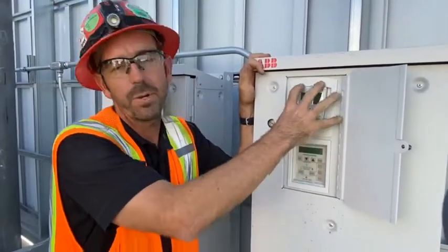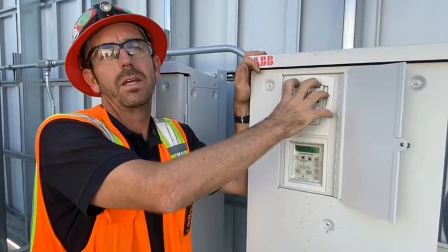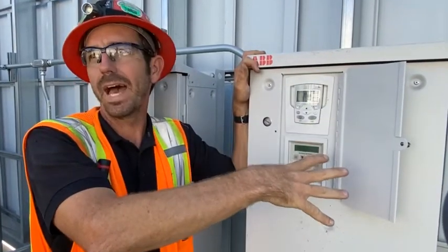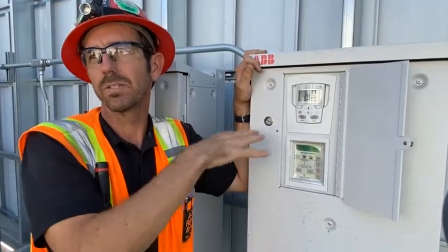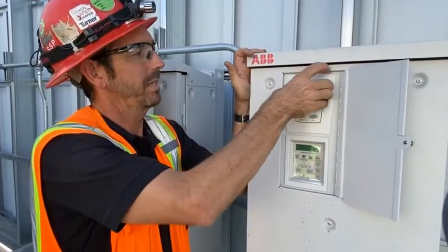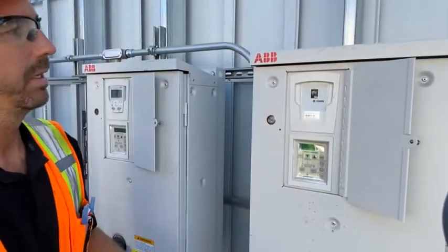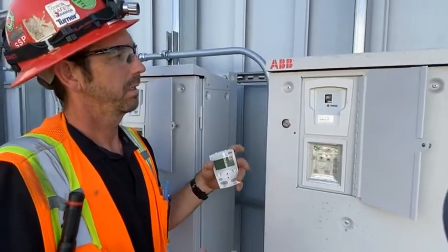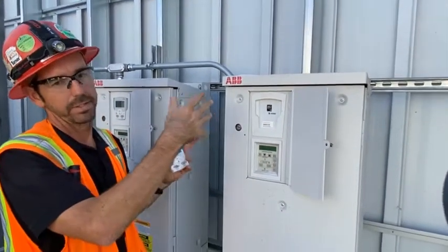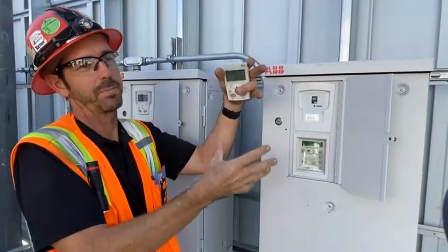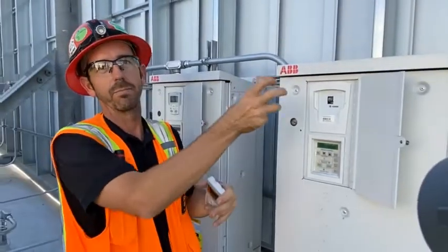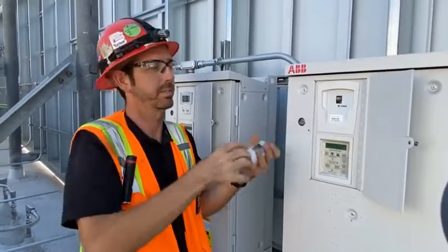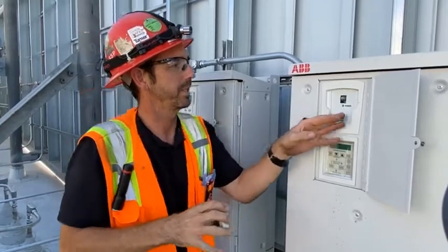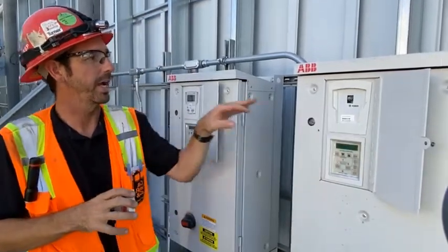Now that all of our changed parameters are stored in the keypad, if the drive ever goes bad, we can turn off power, we can switch the drive out. We take this keypad off. Well, you could leave the keypad on in this application. Normally, if the keypad was attached to the drive itself, you would take it off and put the new keypad on the new drive, right? This can stay there. What we want to do is, since I did make this change here, I can change it over here.